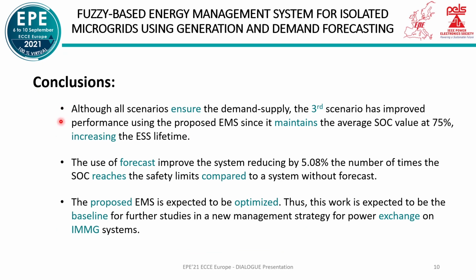Although all scenarios ensure the demand is supplied, the third scenario has improved performance using the proposed energy management system since it maintains the average state of charge value at 75%, increasing the energy storage system lifetime. In addition, the use of generation and demand forecasting improved the system, reducing by 5.08% the number of times the state of charge reaches the safe limits, compared to a strategy without forecast.